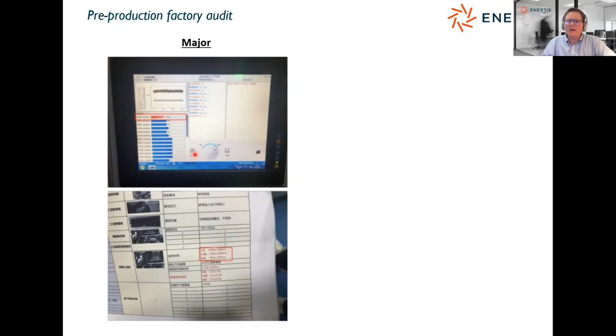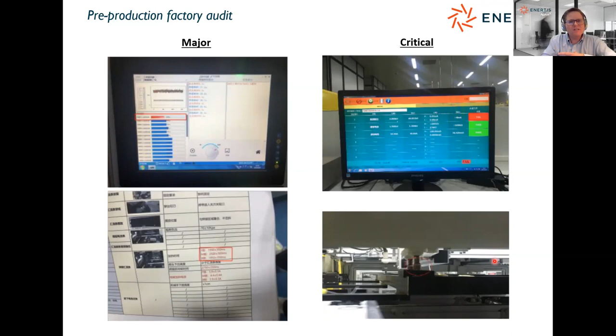Then a critical finding: here's an HMI of a high pot insulation tester. It was found that these probes were not making good contact on the frame, and as a result, everything was going to pass whether or not it should be failed. This results in potentially modules that will cause ground faults in the field and electrocution risk. This is a critical finding that needs to be remedied immediately. That's the whole point, to find the big risks in a factory, highlight them, and correct them before production starts.